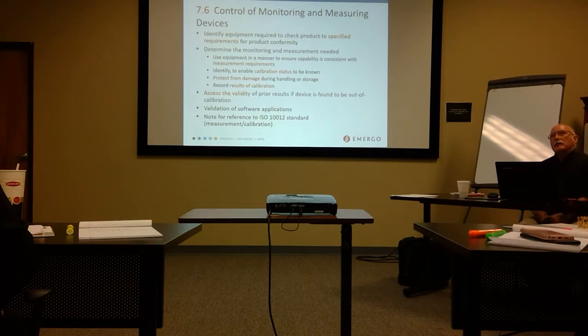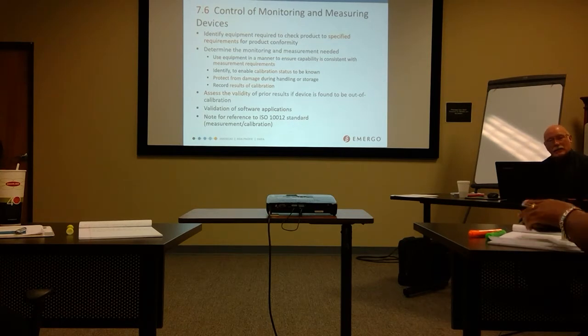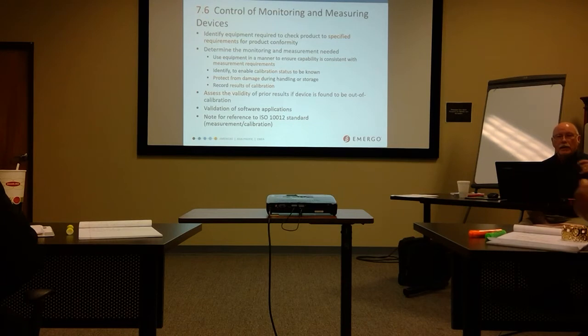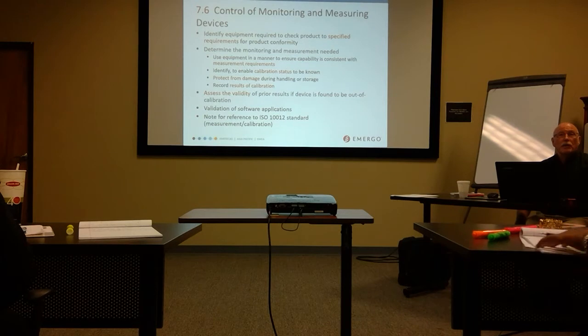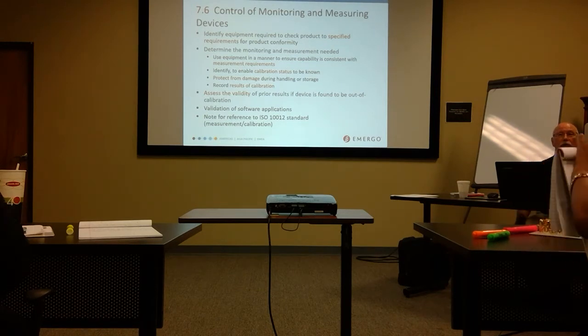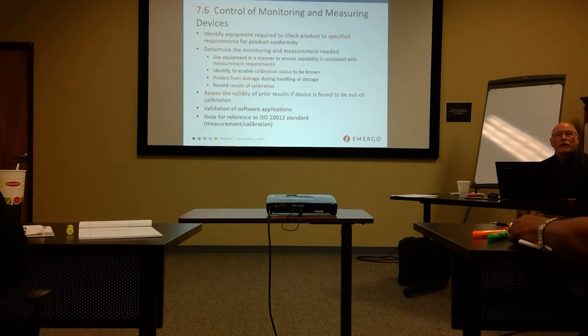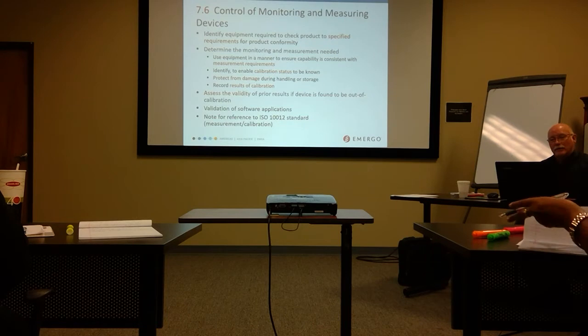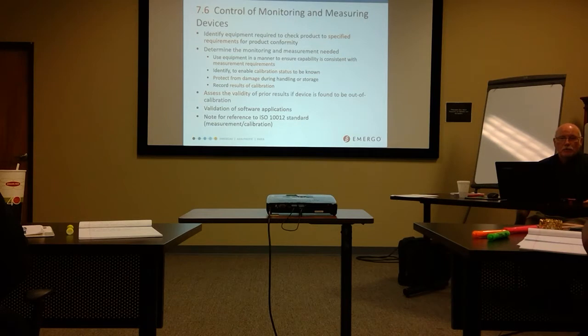The other requirement is that the equipment that requires calibration is described and listed, usually on an equipment list or calibration list, which identifies the instrument down to the specific instrument. Every one of these should have a unique ID. Usually the finance people want that anyway. They'll make you have an asset tag so that they know what we have and to make sure stuff doesn't walk out the door. If you've got 15 digital calipers, they better all be individually numbered. You have to be able to discriminate among them.